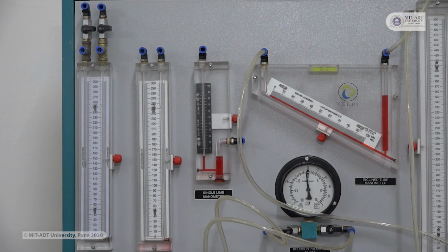If the system pressure is below atmospheric pressure, it means the air present above the liquid column in the right hand side limb of the manometer is atmospheric, whereas the pressure acting on the fluid in the left hand side is below atmospheric. So this air forces the fluid in the right hand side to move downward, and the fluid in the left hand side limb rises and we get a level difference. Using that level difference we can calculate the system pressure.